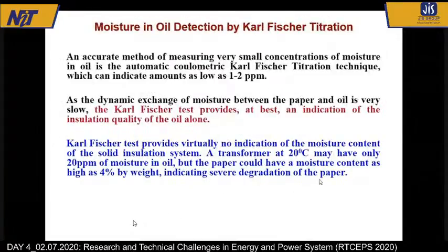So how do we find moisture in oil? This is typically done by a titration technique. We open the oil drain valve and take a sample. But this generally gives only a value for the oil, not any specific location; it gives an overall value.